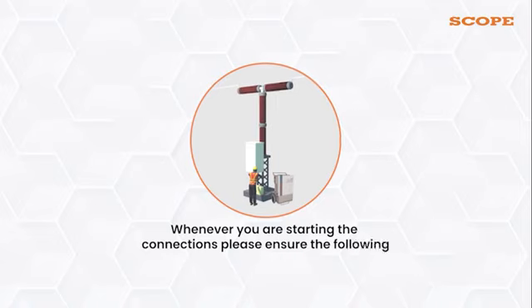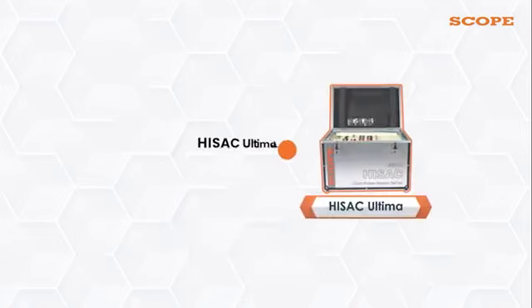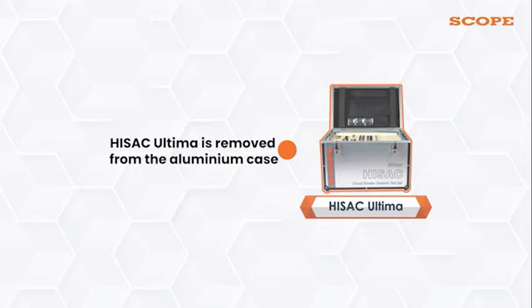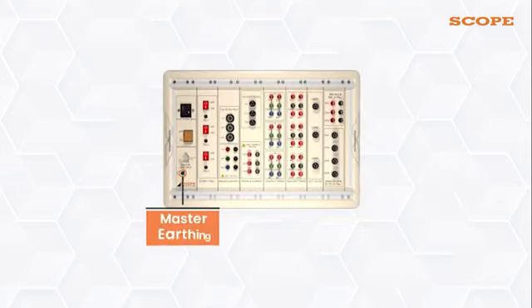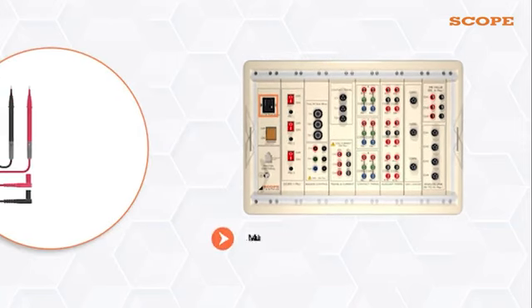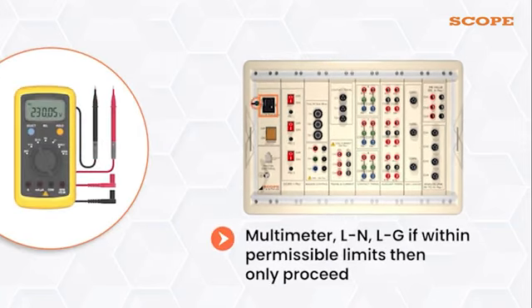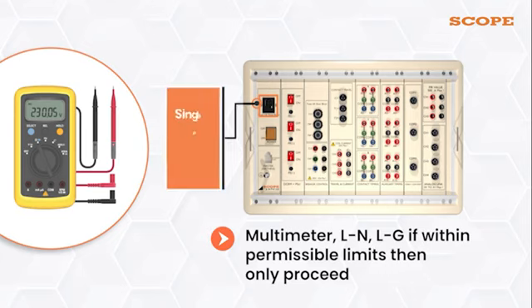Whenever you are starting the connections, please ensure the following. HISAC Ultima is removed from the aluminum case. Connect the master earthing. Check the power supply voltage with the help of any multimeter, line to neutral and line to ground. If within permissible limits, then only proceed. Connect the power cord at HISAC Ultima first and then at the source. Now we need to take control of the breaker. But before that, wait.